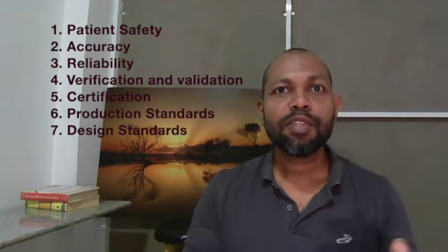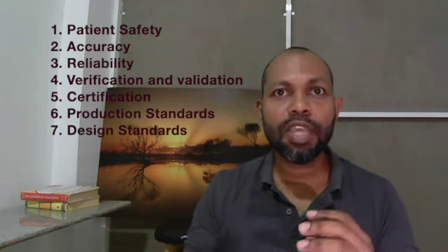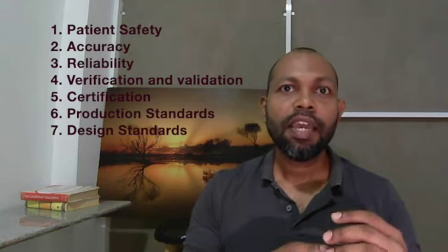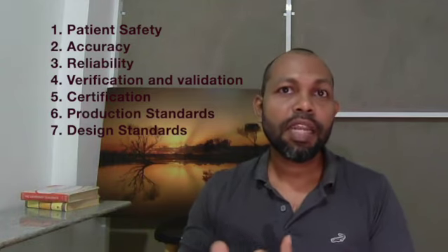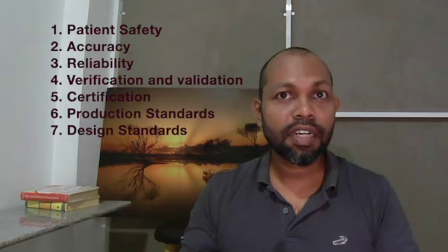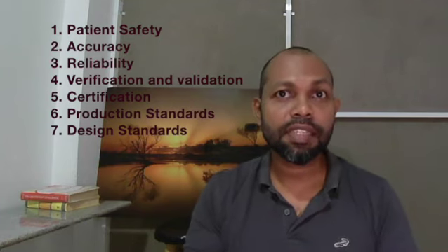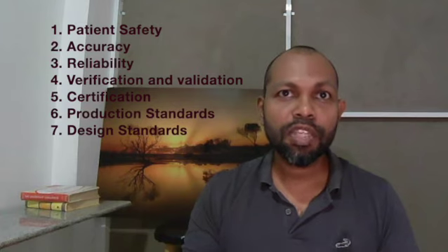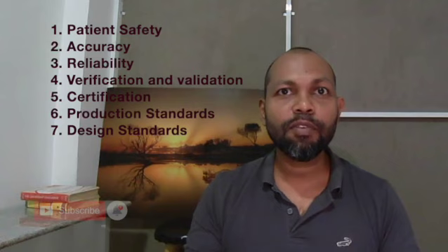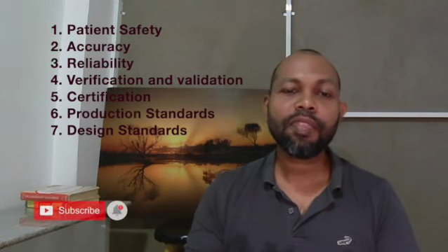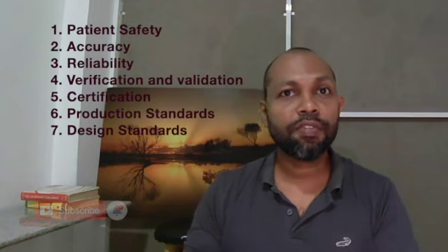Then we have to verify and validate all these achievements and metrics that we defined in the beginning. Throughout the development process and pre-certification process, we have to verify and validate all these parameters we set forth. That validation and verification process is really lengthy and comprehensive, and certification agencies like the FDA look for this verification and validation documentation and make sure that the product developer developed this properly. And then after all these things, we have to push the product for certification.